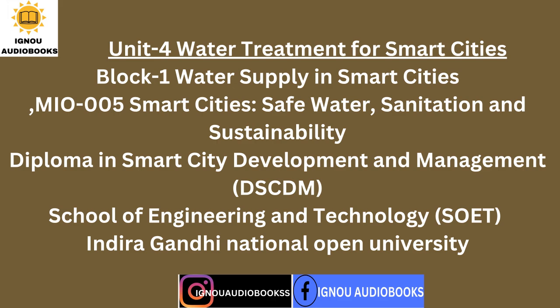These screens are designed to increase the efficiency of screening by reducing the problems related to maintenance and operating. These screens are classified into 4 parts. 1. Chain-driven screens. These screens work as an automatic chain to clean the screen. It is classified into front chain-driven screens and back chain-driven screens based on how the raking of the screen is done from the upstream or downstream, and whether rakes return to the bottom of the bar screen from the front or back.